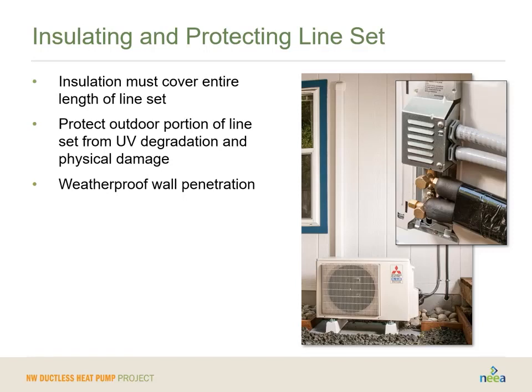We do also want to make sure that this line set is fully insulated, as I mentioned. And it's not just that it's insulated. We also want to make sure it's got UV protection on it. And there's a couple different ways. You can buy line set that comes with UV protection. You can put a UV protection tape over the insulation, or you can put a line hide, which we'll show in a few minutes, which really gives the ultimate in protection and really improves the looks. We also want to make sure that you have a weatherproof wall penetration. Since you're going to have to run that line set and the electrical through that exterior wall, you're going to want to make sure you get it really weather tight. We don't want water or insects or air moving in and out of the walls due to this installation.